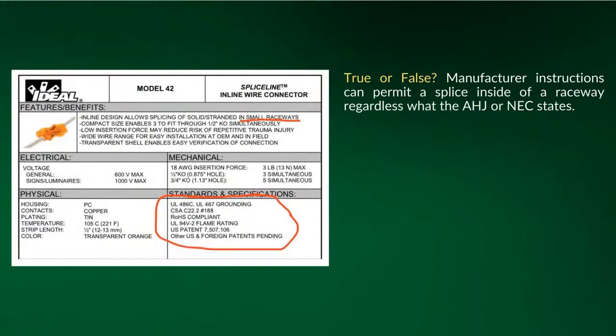This comes from a post in NEC for Dummies that a lot of people probably saw. A guy said he was arguing with the inspector, and the manufacturer instructions say it can be installed in short raceways. It gives a UL number, and I went and looked that UL number up, and I didn't see anything that said it could be installed in a raceway. There's a difference - this might be saying you can splice these in short raceways, but that's in a dry location.